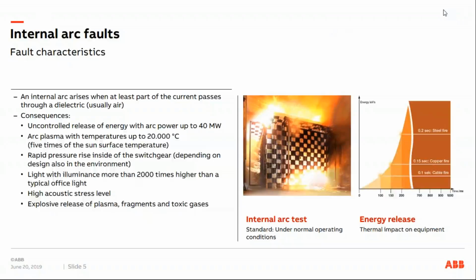On the right-hand side, what you can see here is the energy release for cable fire, copper fire, and steel fire, and the arc fault is even above all of that, what we can see here.